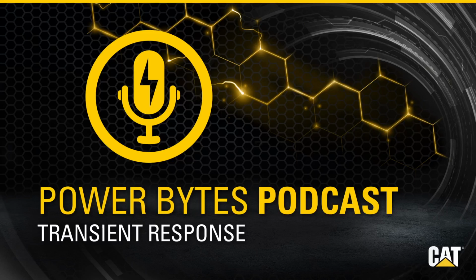So the engine will continue to increase fuel and air until it reaches its maximum fuel setting. During this period, the speed will return back to the steady state settings, and the fuel will then reduce back to a steady state operation with a new BMEP and a new power level to support that new level of load. Thanks, Bryan. I think I understand that a lot better now.